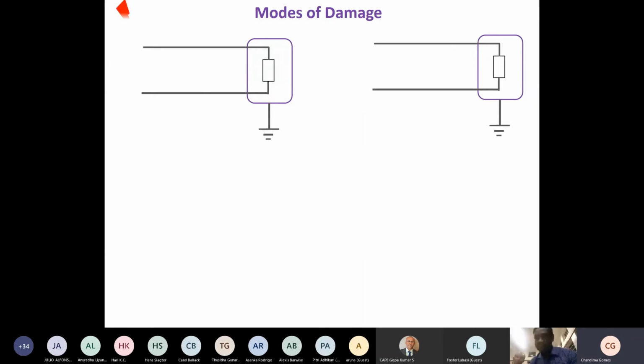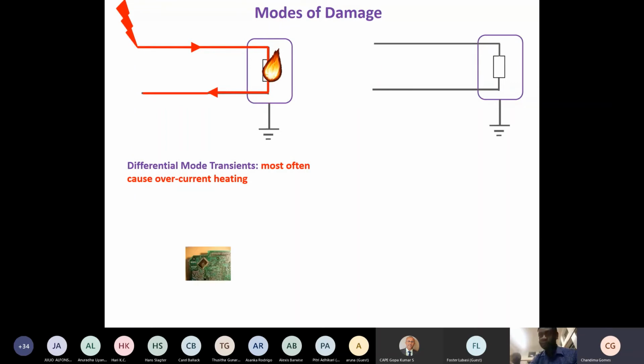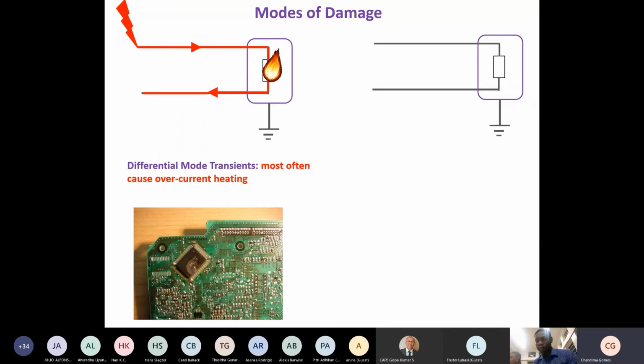There are basically 2 ways. One is if lightning strikes a power line, either the line or the neutral, basically the line, then a large current may pass through your equipment. We call it a differential mode transient because now you have a potential difference between your line and neutral. And most often that causes overcurrent heating, and you see melted parts in your equipment when you have differential mode transients.